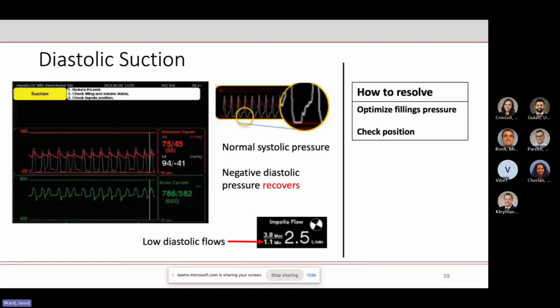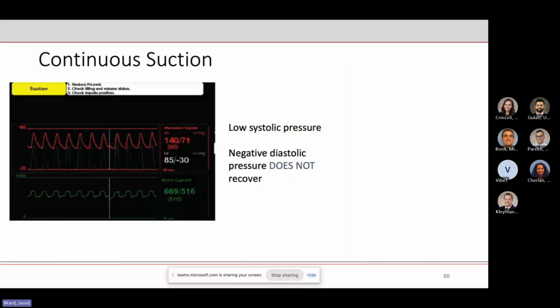Yeah. So basically, with this, the LV waveform will recover in diastolic suction events, and the only thing you'll see, because it recovers, is that your systolic pressure will remain normal, but your diastolic flow will be less. Versus with a continuous suction event, the LV waveform does not recover. There's no overlap between the LV waveform and your aortic waveform, and that's just because this is a constant low flow issue.